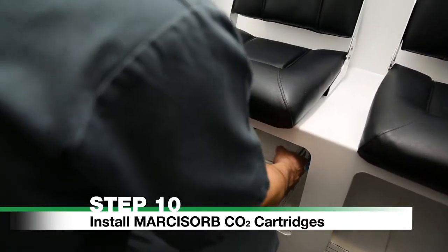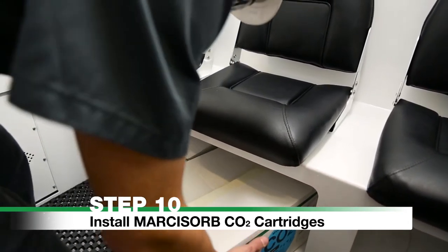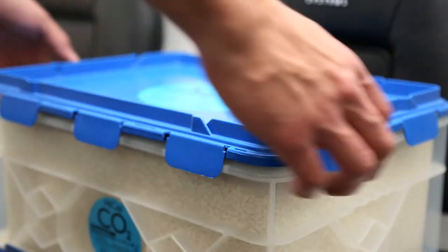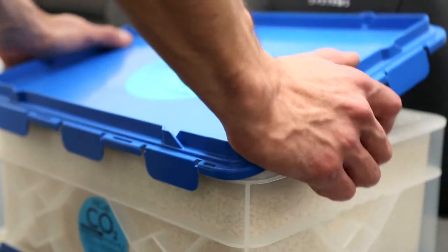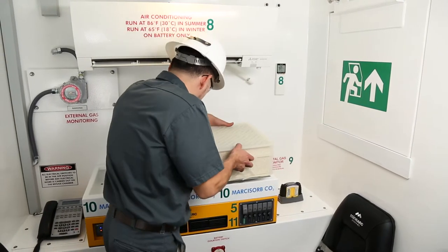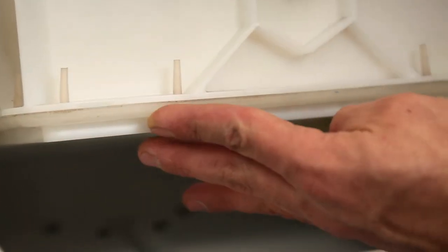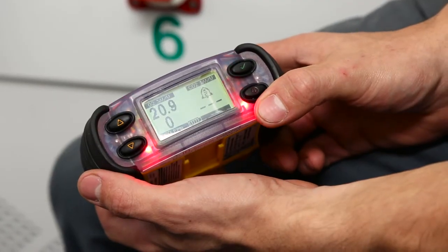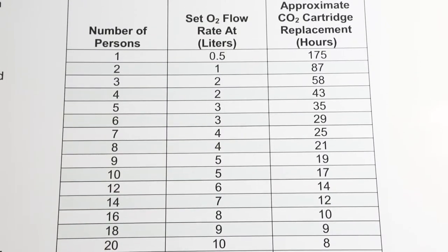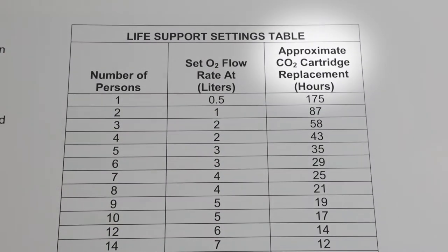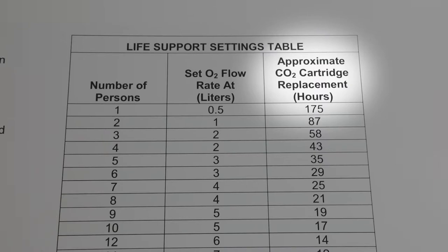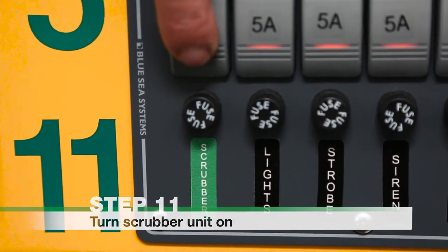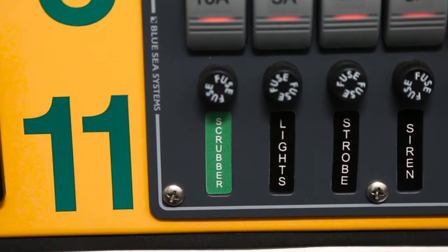Step 10: Install Marcisorb CO2 cartridges. Remove three Marcisorb carbon dioxide cartridges from their storage location and remove them from their packaging. The cartridges will slot into place with the rubber seal on the bottom side. Replace the cartridges when the gas monitor reads CO2 as being greater than 1%, or as indicated by the life support settings table on the safe haven wall. Step 11: Turn the scrubber unit on by activating the switch marked Scrubber on the front panel.